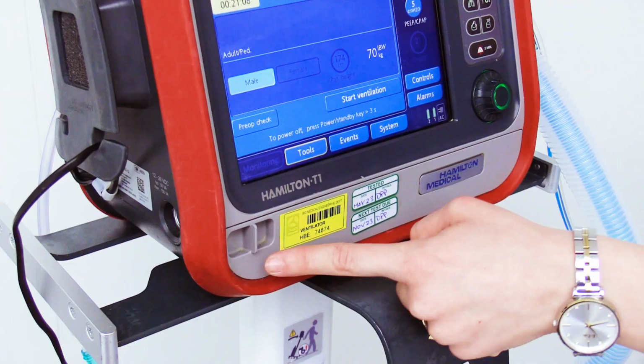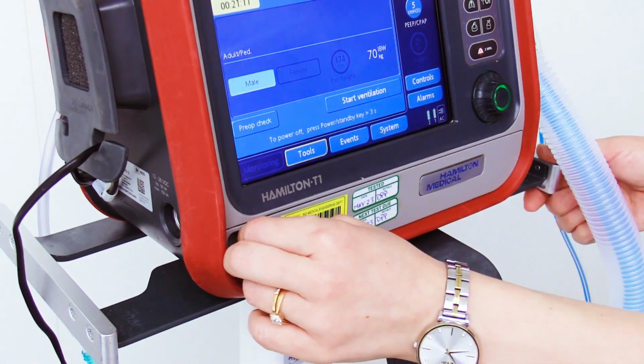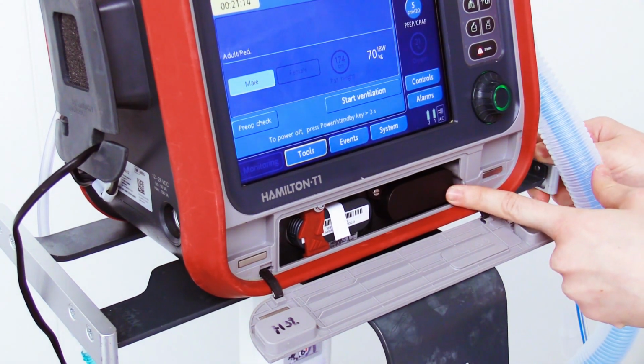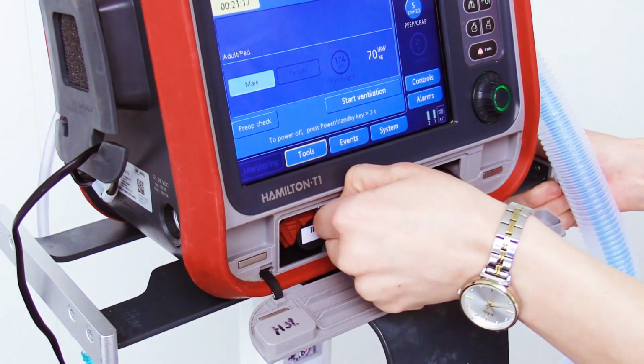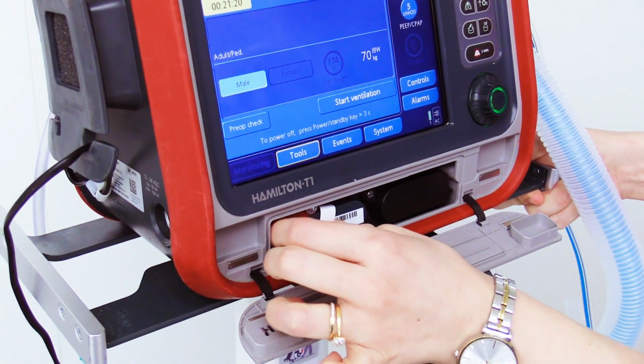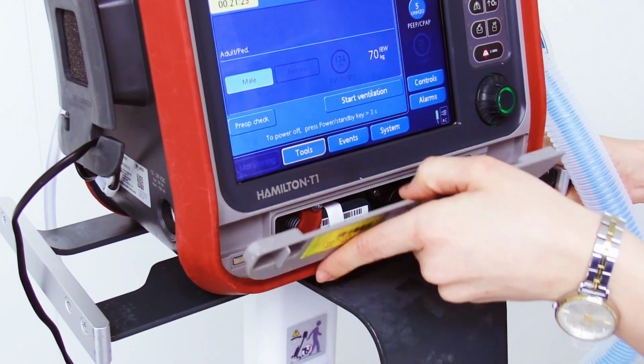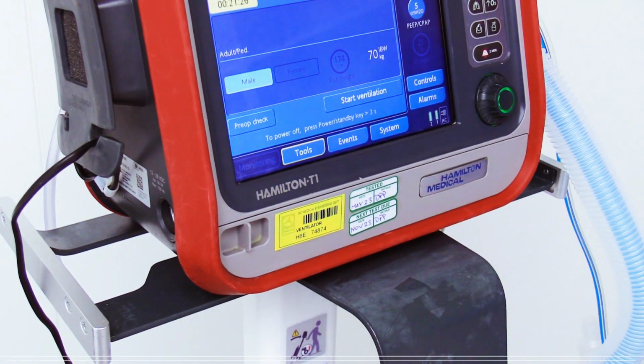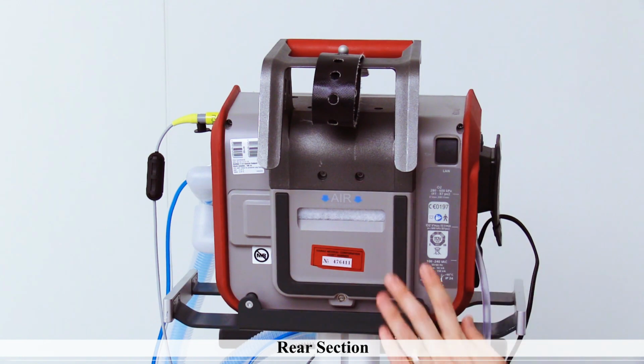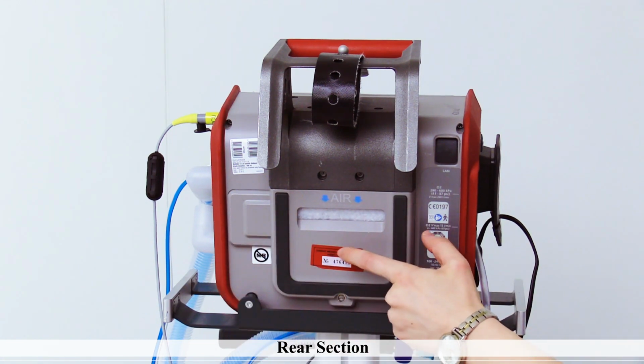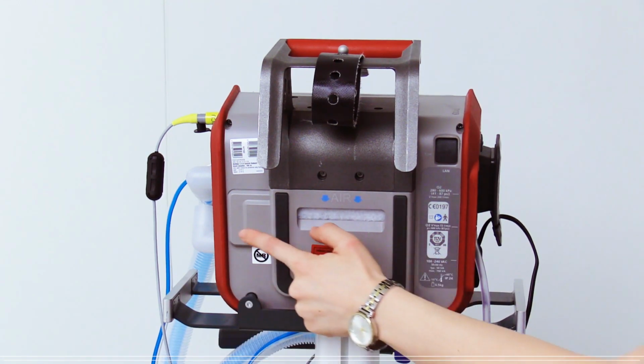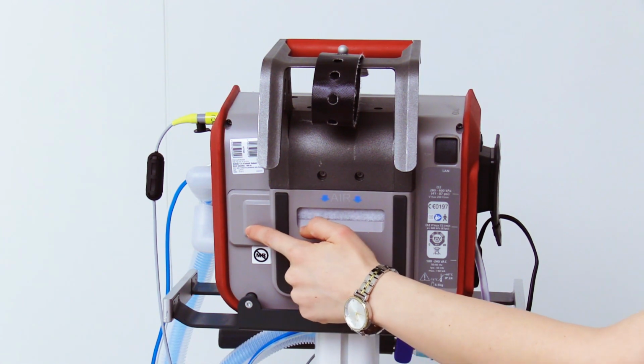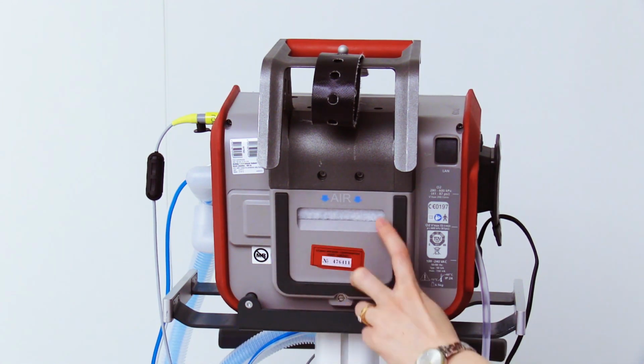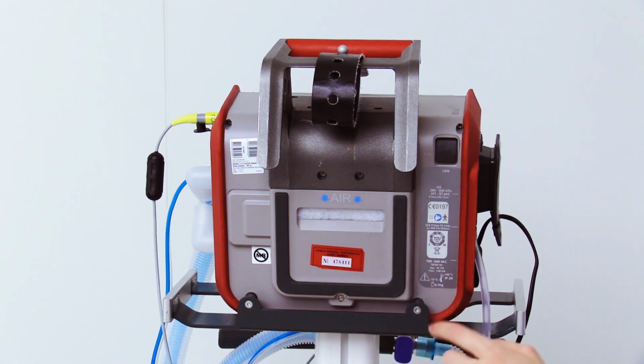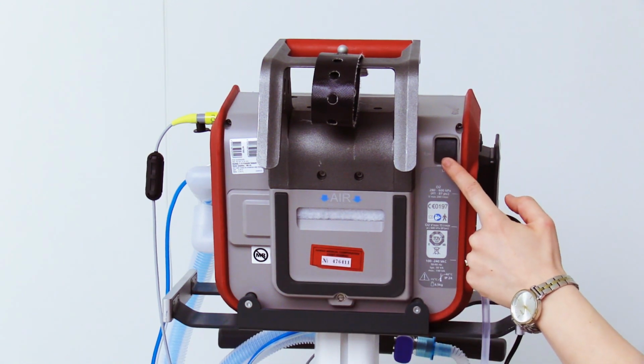And here, we find the front cover with 2 batteries under it. One is fixed, and one is portable. Each battery is good for about 4.5 hours, together approximately 9 hours. On the back of the ventilator, we find a rear cover. Behind this cover, there is a HEPA filter and an O2 sensor here. Also, there is an air intake and dust filter. And here is a LAN connector for service.